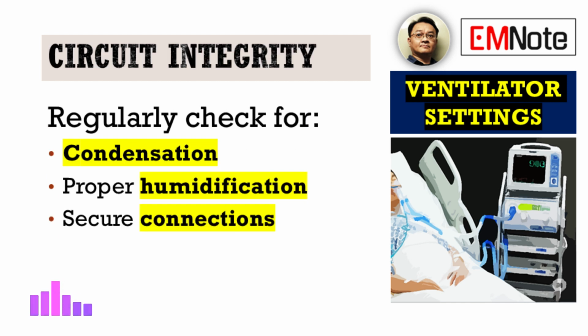Makes sense. Beyond just reacting to alarms, what about maintaining the overall integrity and function of the breathing circuit itself as part of ongoing safety checks? Absolutely. Maintaining circuit integrity is vital. You need to proactively manage it. Regularly check the breathing circuit for condensation water buildup, which can accumulate within the tubing. Excessive condensation can actually impede gas flow, or worse, become a breeding ground for bacteria, increasing infection risk. Drain it carefully. Ensure proper humidification is consistently maintained. This prevents airway drying, which can damage the patient's respiratory mucosa, lead to thick secretions, and increase infection risk too. And lastly, continuously verify that all connections within the circuit remain secure. Tighten them if needed. Any loose connection can quickly escalate into a leak or even a full disconnection, compromising the patient's ventilation. So it's clearly not just about reacting when an alarm goes off, but also proactive, ongoing maintenance to prevent issues from even arising in the first place. Exactly right.